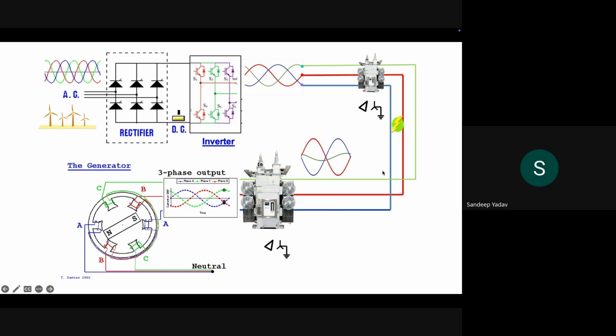So, for example, this is the case of a phase-to-phase fault in R and Y phases. If a phase-to-phase fault happens, it is very safe to assume that the synchronous machine will feed a fault wherein the fault current in R phase will be 180 degrees opposite from the Y phase. So R and Y, both phases, will have a 180-degree phase shift, and the B phase will be more or less unaffected, depending upon the grounding of the system, because it is usually solidly grounded.